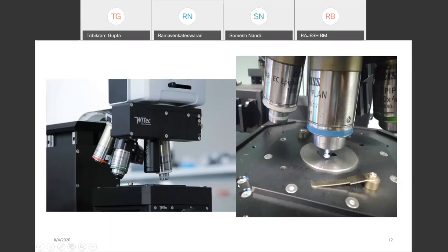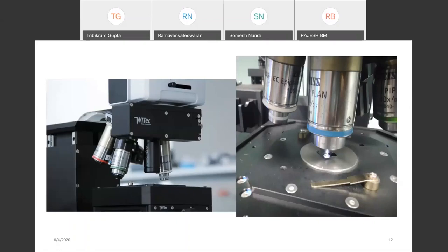What are the optics for sample illumination and light collection? Light from the illuminated spot is collected and guided through an interference filter or spectrometer to get the Raman spectrum. Bandpass filters are used to isolate a single laser beam. A combination of notch filter and high-quality grating monochromator is mostly employed in dispersive instruments. Double or triple grating monochromators are used to separate relatively weak Raman lines from intense Rayleigh scattered radiation, since the Rayleigh signal is very strong compared to the Raman signal.